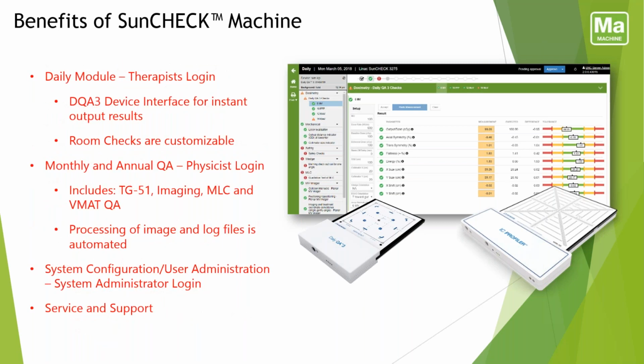The daily module is accessed through therapist login, and the DQA3 device interface allows for instant output results. And the room checks, mechanical and safety, are all customizable. So we were able to get all of our tests configured the way we want them. It also has all TG142 tests, so we have the imaging isocenter accuracy and repositioning tests all included in the daily module.